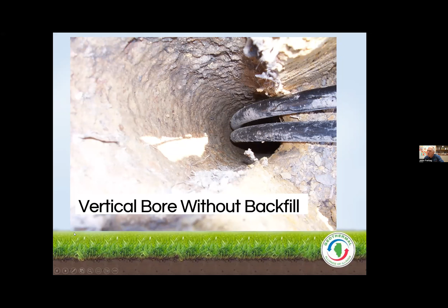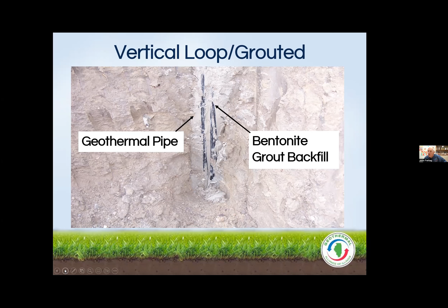That's important for two reasons. Number one, it makes the system much more efficient - how efficient would it be if you just had air in that borehole? Wouldn't be very efficient at all, you wouldn't have a good heat exchange. Or if you just had sand dumped into the borehole, it wouldn't be very efficient either. So the bentonite grout ensures really high efficiency and heat transfer into the ground. Number two, and probably even more importantly, it ensures there's no groundwater contamination. So grouting is done for two reasons: safety for our groundwater tables, and heat transfer.